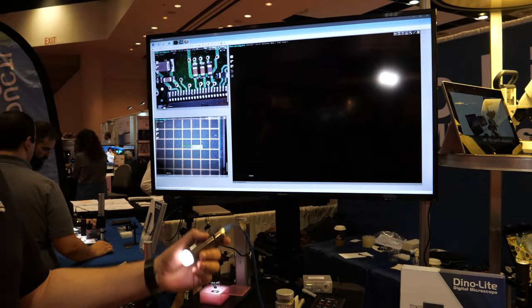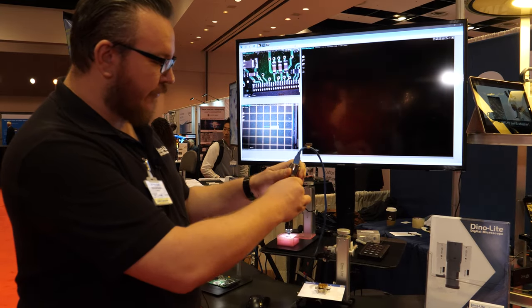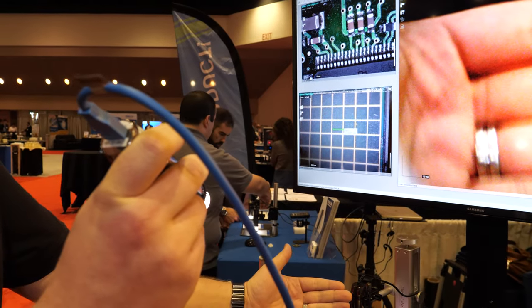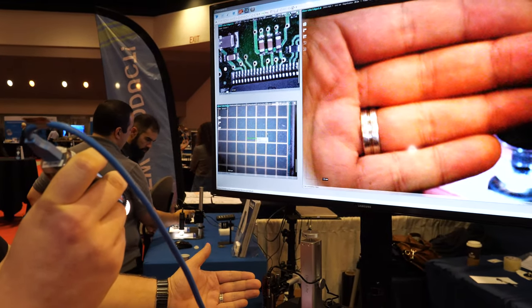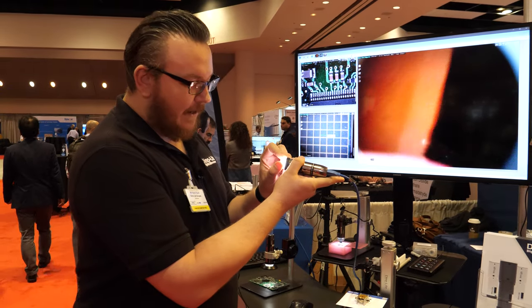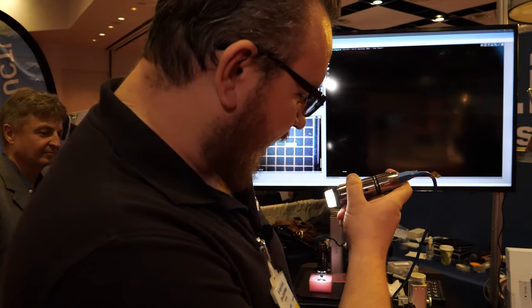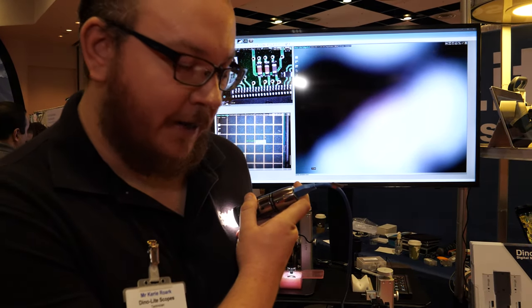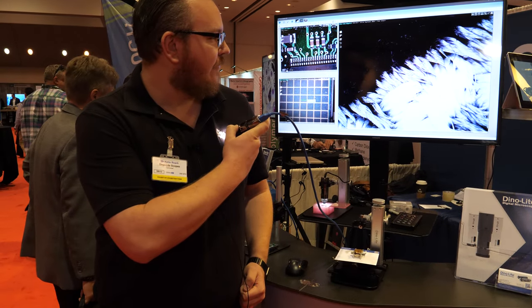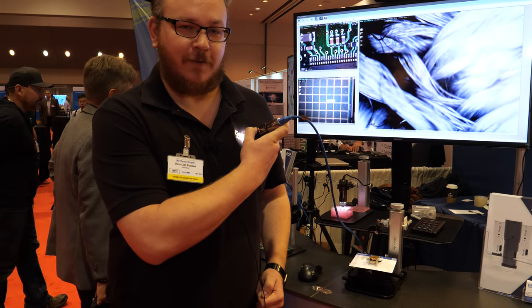How do you adjust the variable magnification — do you just turn it? Yes. To adjust the magnification, you have to adjust both the working distance and then turn this dial here on the side. These can focus to infinity — it's not made for that, but I can have a very large field of view if I'm far enough away. These caps here on the end are made at a specific distance so that if this cap is in contact with the surface, it can focus at 50 times and again at 200 times without having to adjust the working distance further.